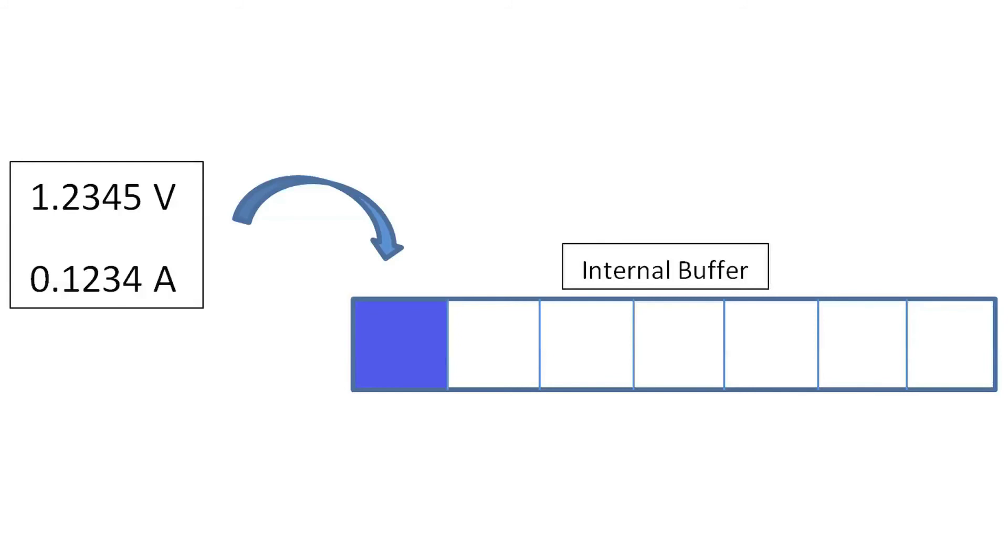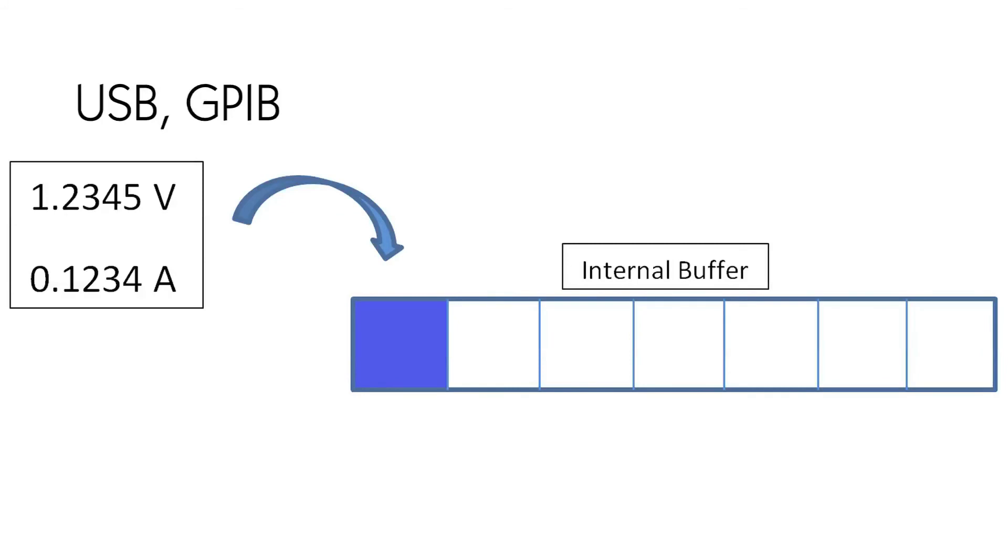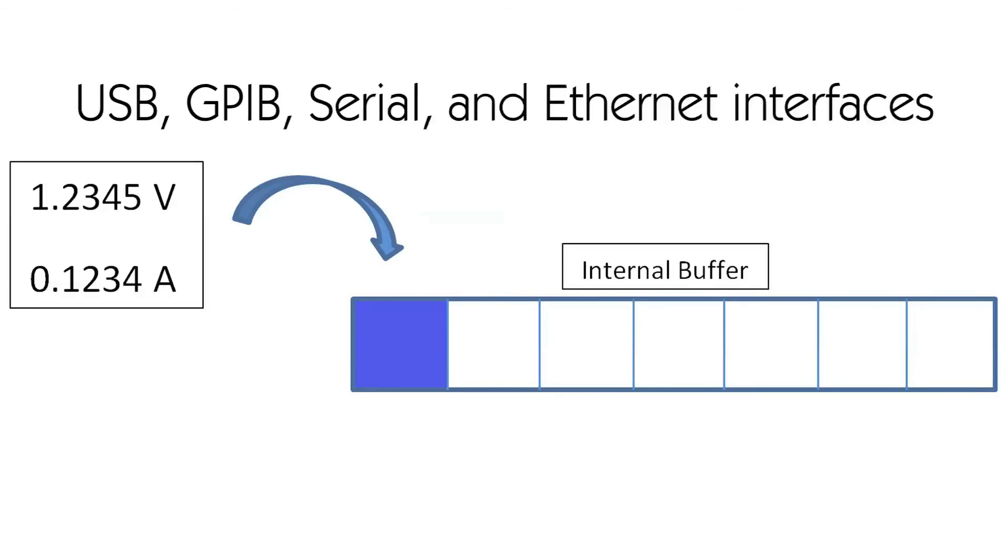The main advantage of this operation is speed, because all measurements are directly stored into the internal buffer without any additional post-processing time, which is present when acquiring measurement data using USB, GPIB, serial, and ethernet interfaces.